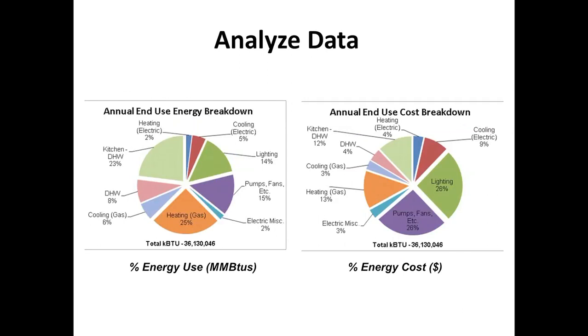Breaking up further, using the chart that's 2 slides back, you can see the breakout when we include domestic hot water: you have gas, pumps, lighting, cooling electric, heating electric. I'm looking at it again from an energy use versus an energy cost perspective. If we were to make some improvements on heating, we would think that we'd have a big percentage of cost savings because heating occupies 25%. But from a cost perspective, total heating usage for gas is only about 13% of the total energy bill.